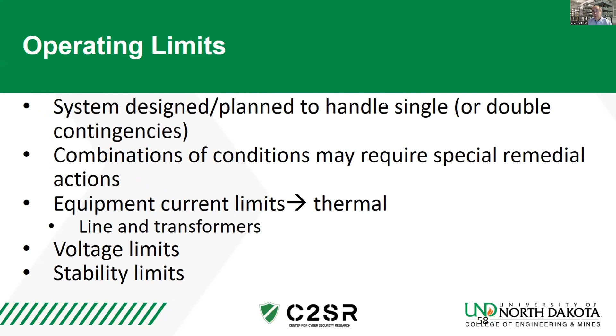When we're doing limits, we have to have the system be able to handle single, and most of the US, double contingency. So this is a what-if scenario: what if this line trips and this line trips, or this line and this generator trip? You don't want to have the system go out. If that equipment does go out and stays off, then you have to update your calculations with that off.